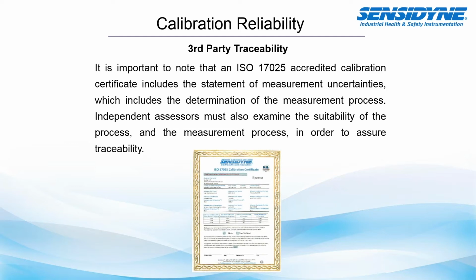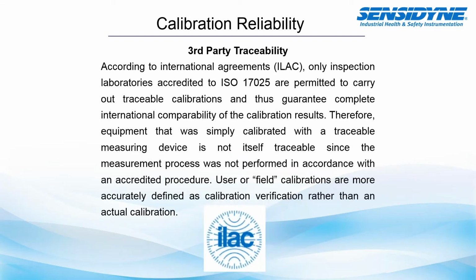This is a determination of the measurement process, and independent assessors must also examine the suitability of the process and the measurement in order to assure that traceability. So this is where calibration laboratories are audited by another third-party group to ensure that they have a sound process and that the traceability of the units that go out the door that they calibrate can actually conform with the national standard, and in this case, to NIST. According to the ILAC, only inspection laboratories accredited to the ISO 17025 are permitted to carry out traceable calibrations and thus guarantee complete international comparability of the calibration results.